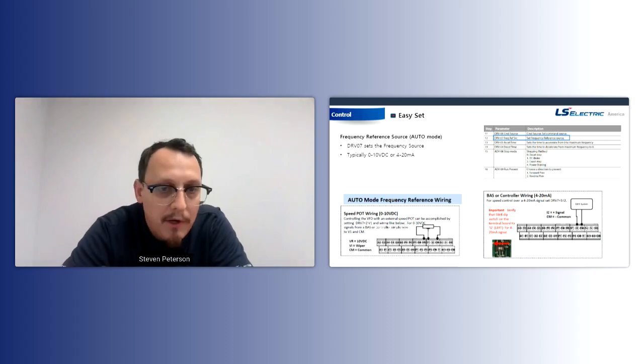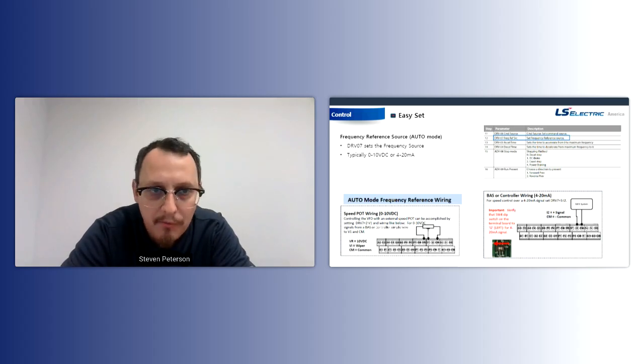Contrary to that, you could be running a 4 to 20 milliamp, and that would go to terminal I2. So you'd go to the same parameter and you say go to I2, and then the drive looks at its 4 to 20 reference. So DRV 6 and 7, you're really just pointing the drive at, hey, what terminals are you going to look at to start and stop and control the speed? Okay. So you get through those two, that's your basic controls.